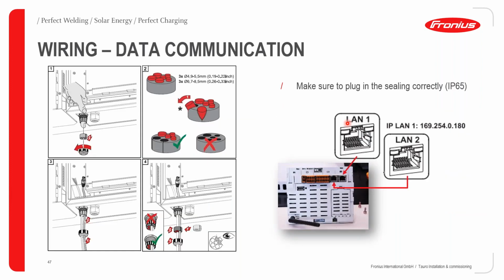For your data communication, in terms of your wiring, please make sure that you do follow these specified guidelines. So if you are going to, for example, add an Ethernet cable, only pop out a section that you are using. Okay, so don't pop out each section, only pop out a section that you're using. The reason for this is in order for the inverter to maintain its IP65 rating.